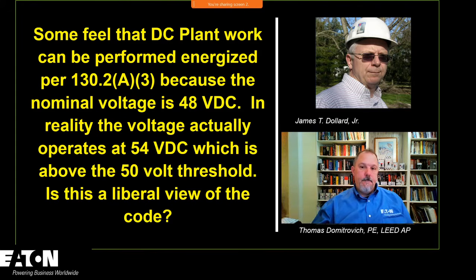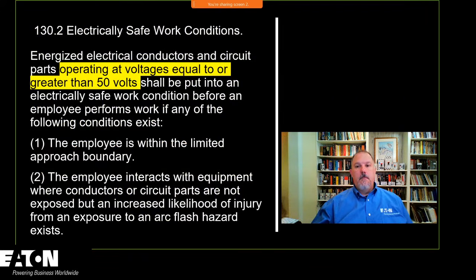Yeah, when you get into 130.2, one of the things we're doing here, and Tom, this was a very interesting question when I looked at it, because we've got nominal voltages. We use that all the time in the National Electrical Code, and one of the nominal voltages is 48 volts. But a couple cycles back, because of the float voltage, and there's an informational note in the NEC that says it could go up as high as 58, we use a nominal 60 volts there now, because we understand that it does go above 50.